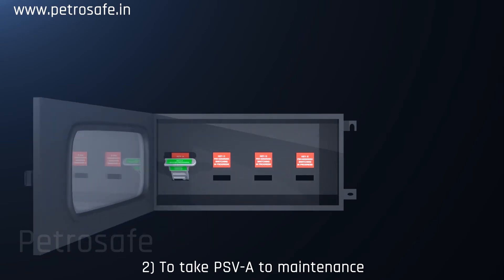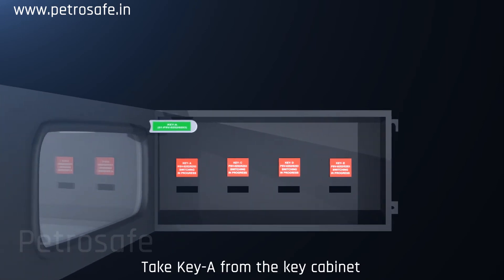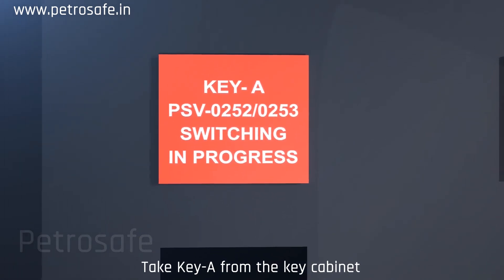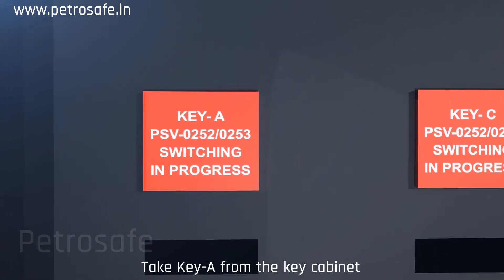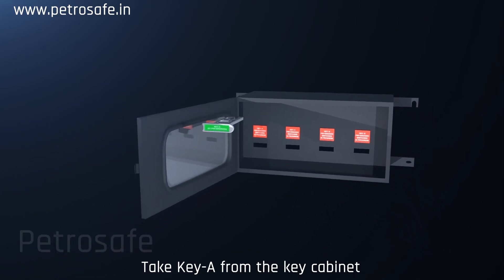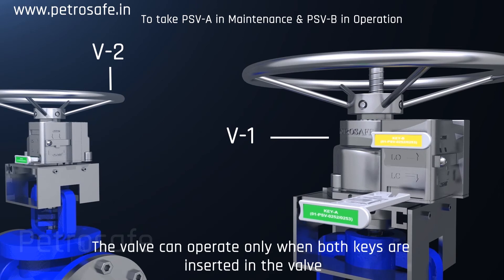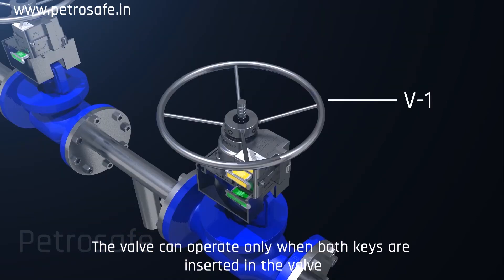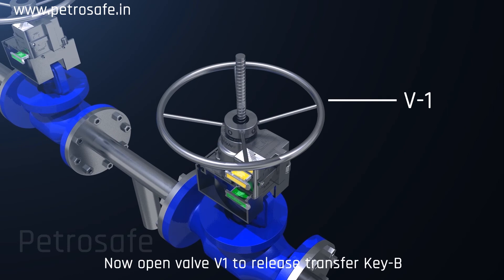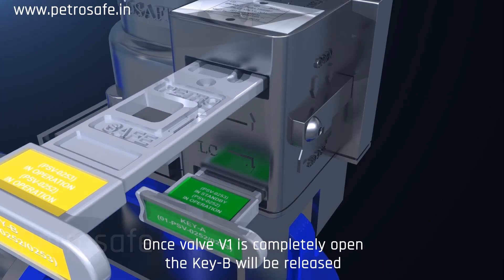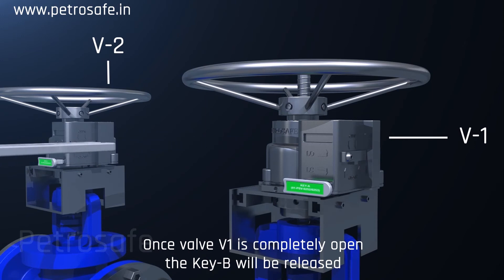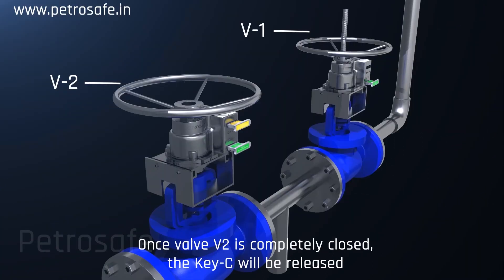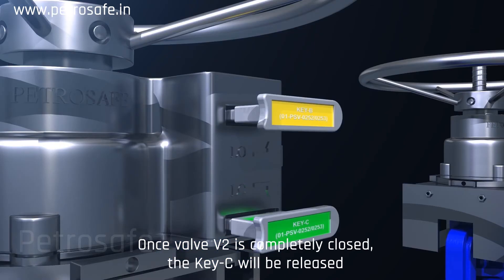Step 2: To take PSV A to maintenance. Take key A from the key cabinet and insert it into valve V1. The valve can operate only when both keys are inserted. Now open valve V1 to release transfer key B. Once valve V1 is completely open, key B will be released. Remove key B from V1 and insert it into valve V2 and close the valve. Once valve V2 is completely closed, key C will be released.